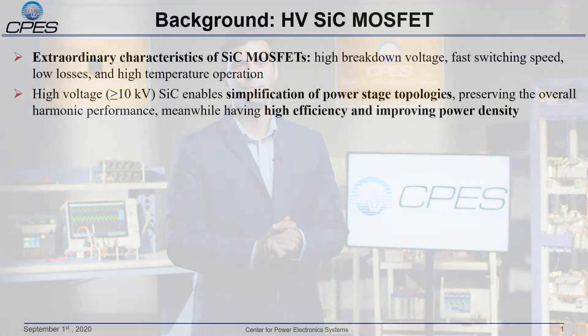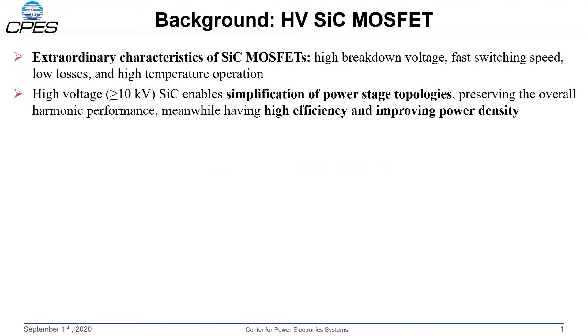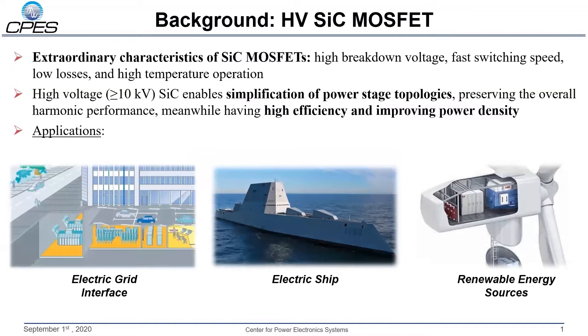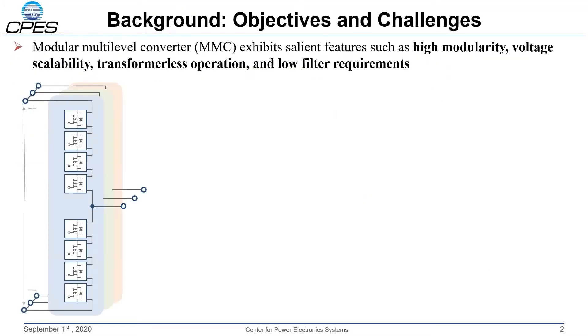In this video, I will be talking about the assessment of a medium-voltage power cell based on a high-current 10 kV silicon carbide MOSFET half-bridge module. High-voltage, fast-switching, low-loss silicon carbide MOSFETs enable simplification of power-stage topologies, improving power density and efficiency of power electronic systems. This is particularly important for medium-voltage applications where land and space are very limited and expensive, such as MVDC distribution in high-populated urban areas, DC power systems for more electric ships, and renewable energy sources. MMC is increasingly considered due to its features of high modularity, voltage scalability, transformer-less operation, and low filter requirements.